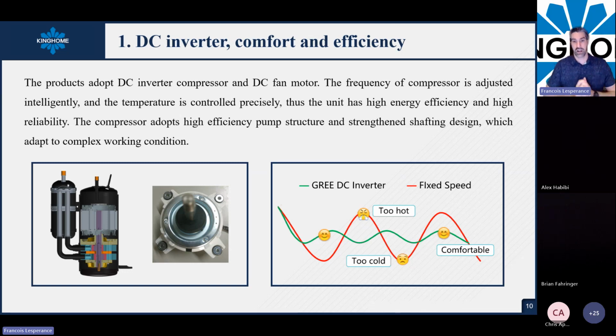So we're using the same kind of compressor and the fan. Inverter, as you may know, the point is the compressor runs more time during the day to meet the set point, reducing and increasing the capacity. The difference with the fixed compressor speed is that it will be on and off and on and off. So this is why we're using inverter technology for every kind of unit now, because we want the compressor to run longer, but with different capacity, to meet the set point.